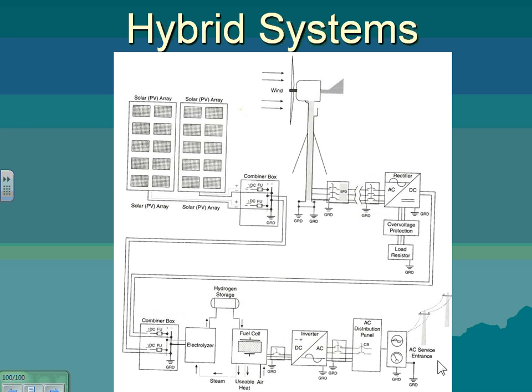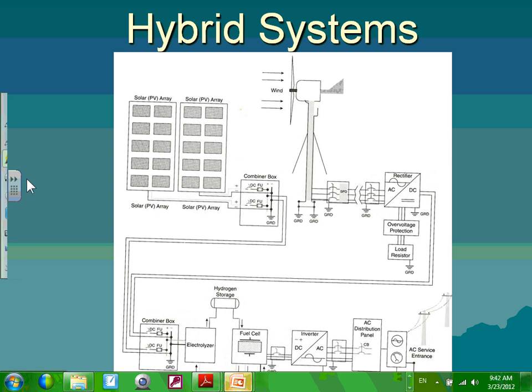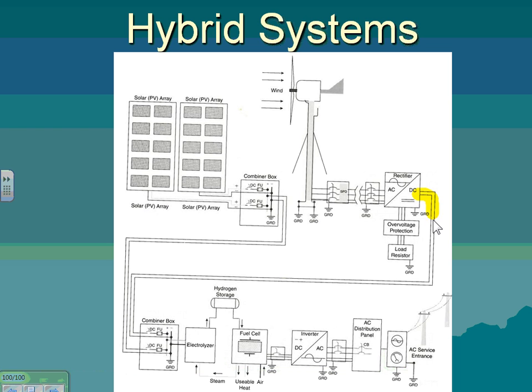So if you look at this one, the way they do it, the wind part, they took the wind here, and my understanding from what I read about this system installed, you take the wind power energy right in here all the way, and they use the wind as a source. See how it's tied together in the combiner, and also these are DC, and they tied these two together on a combiner. That's exactly what you just said. They're tying the two together as DC. DC, no problem. If you have 500 DC, 500 DC, can I put them together, positive to positive, negative to negative? No problem. They tie them together, and they use them to create hydrogen and store hydrogen.